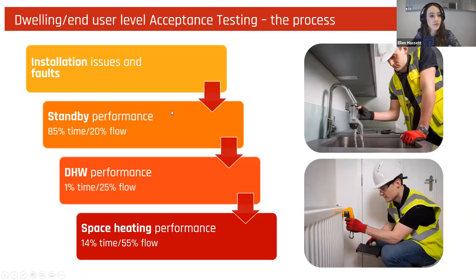Next slide, please. So the process can be simplified to what is seen here. First, we look at installation issues and faults, such as insulation quality. The final run to the HIU accounts for up to 50% of the overall network, and despite this, it's the most common for it to be insulated poorly. So we'll look out for the insulation standard, amongst other faults, such as heat meter errors.